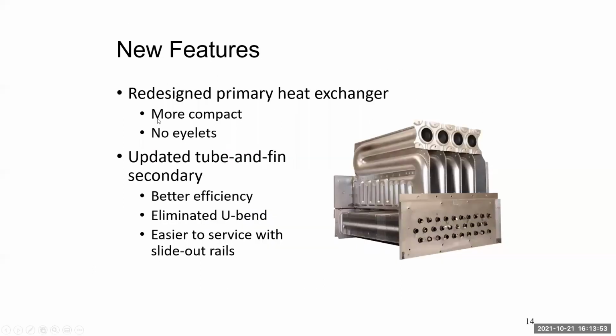Oh, back up too quick. Heat exchangers. Again, this is not new information. It's new features to the 59 series. We're just touching base on them. They're more compact and we got rid of the eyelets. No more cracking rings. And the secondary big thing is they eliminated the U-bends out of them. They are much easier to service now with the redesigned slide outs on them. So it's kind of a piece of cake to get those bad boys out now.